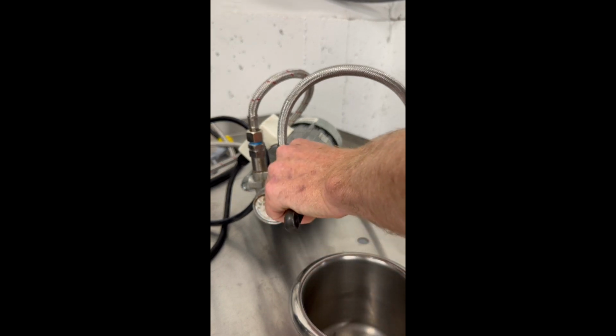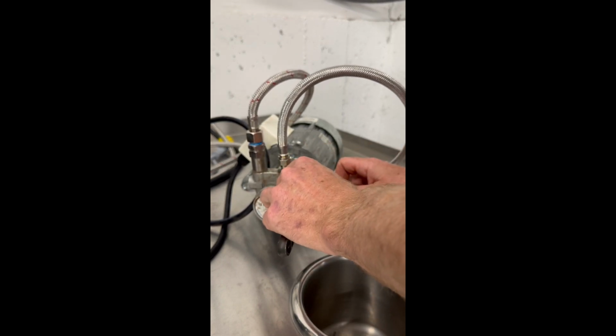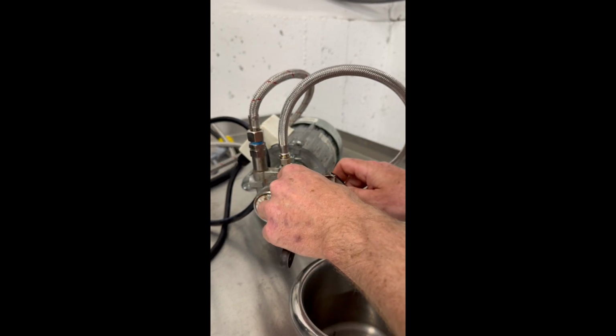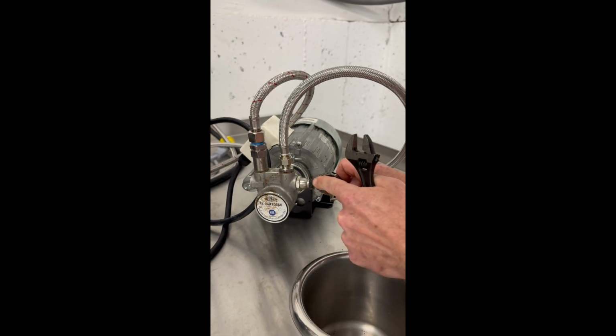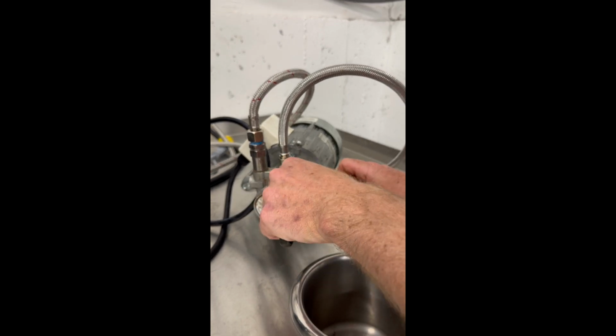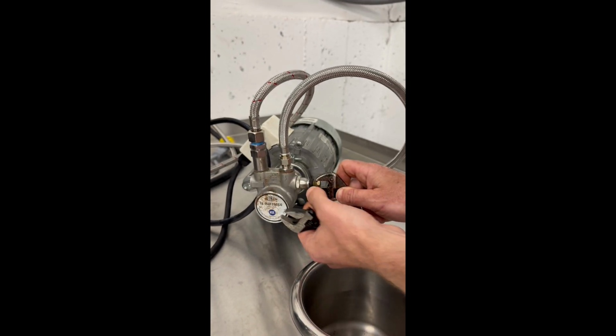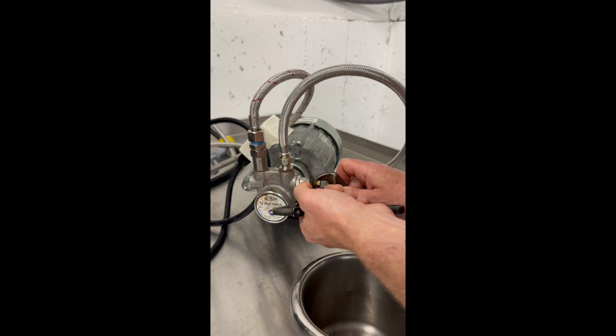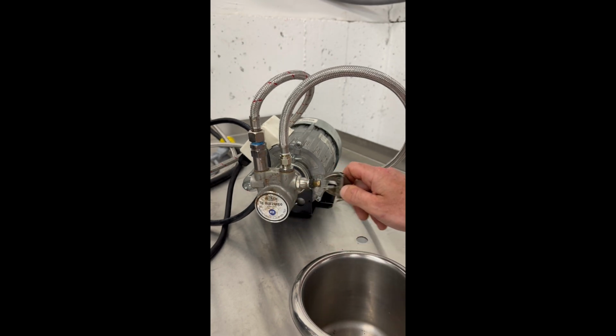And this black nut here is just to lock it into place. So you'll hold down this piece, just kind of hold it steady, get another wrench on here and just loosen this. Doesn't really matter where you go, just get it a little loose. And then you should be able to spin the actual adjustment screw either to the left or to the right. And if you spin it to the left, it's going to make the pump pressure lower. Spin it to the right, it's going to get higher.